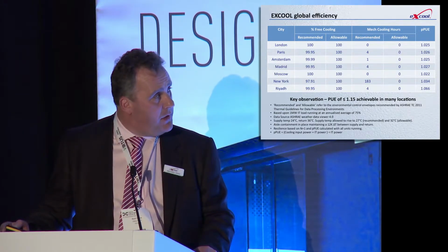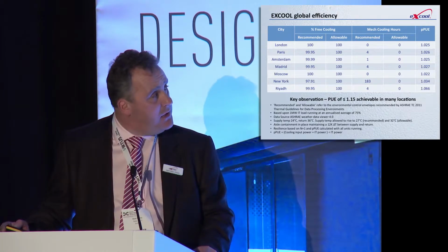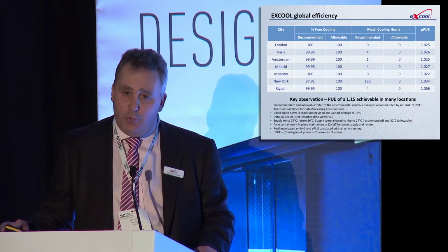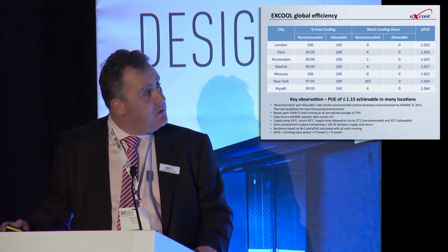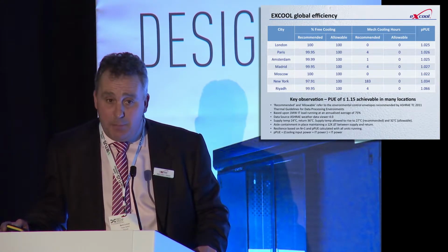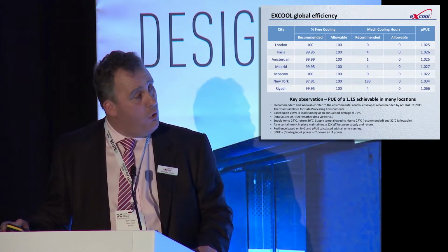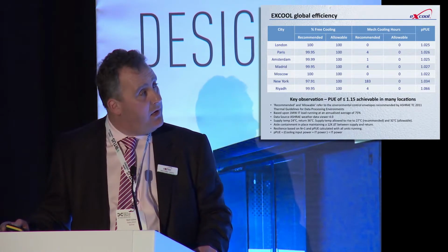And what this table is also showing you is the number of hours that we need to run compressors to maintain 27 degrees C as an upper limit in the recommended column, or 32 degrees C as an upper limit in the allowable column.